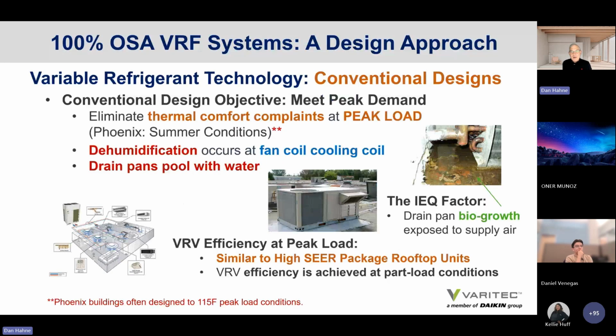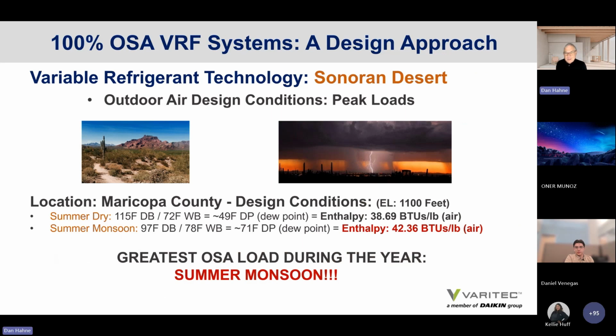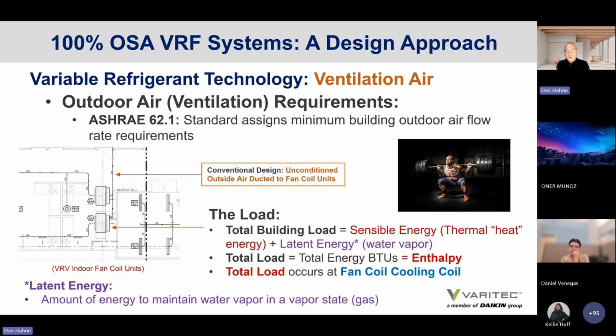variable refrigerant systems. Conventional variable refrigerant systems are designed with untempered outside air. At least that's what I've seen historically in our market, though we're starting to see a shift. These systems are designed for peak summer design load, and consequently condensers using VRV are frequently oversized, which compromises their efficiency and increases the amount of refrigerant required to maintain the system. Be aware our greatest design day is in monsoon, not when it's 115 in June at a 72-degree wet bulb temperature. And if you have untempered outside air serving the fan coils of a variable refrigerant system, that fan coil is handling all the sensible and latent load. It's doing not only controlling thermal energy in a space, but also the amount of humidity in a space. So drain pans fill up with water, and consequently, these systems are rather inefficient.